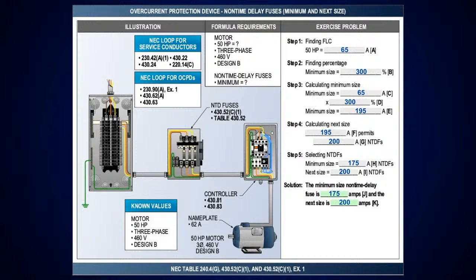Now, when you look at this illustration, we just need to know a couple of values here. We know it's a 50 horsepower motor, 3-phase, 460 volt, design B, and we're going to size a non-time delayed fuse. In step 1, I'm going to get the amperage. Since this is 3-phase, we're going to look at table 430.250, which was permitted once again by 430.6(A)(1). You pick up the 460 volt column, come down, line it up with 50 horsepower, and it's good for 65 amps.